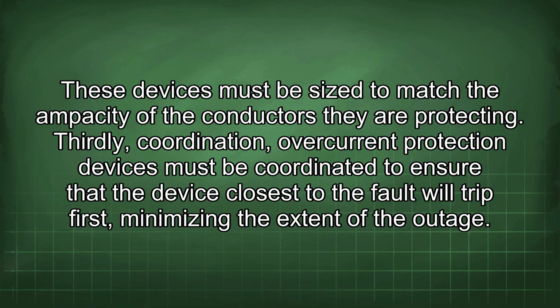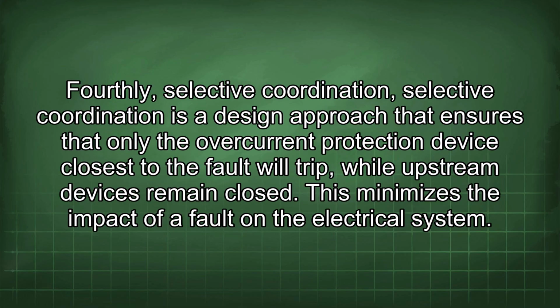Thirdly, coordination. Overcurrent protection devices must be coordinated to ensure that the device closest to the fault will trip first, minimizing the extent of the outage. Fourthly, selective coordination. Selective coordination is a design approach that ensures that only the overcurrent protection device closest to the fault will trip, while upstream devices remain closed. This minimizes the impact of a fault on the electrical system.